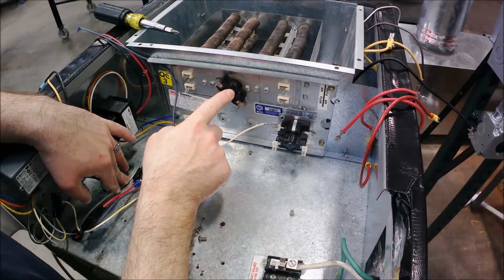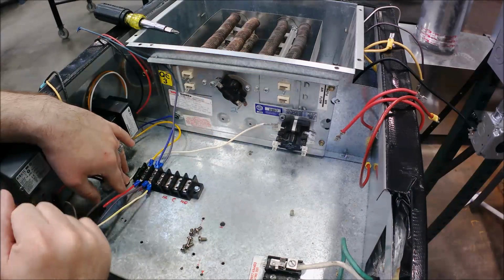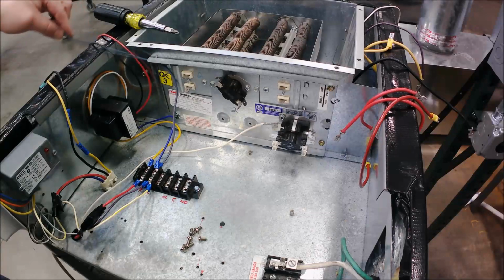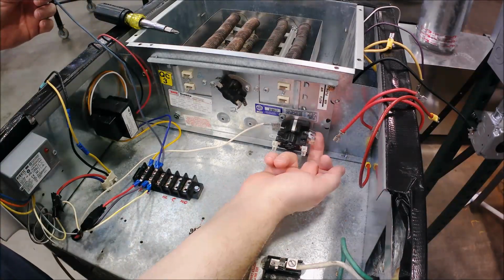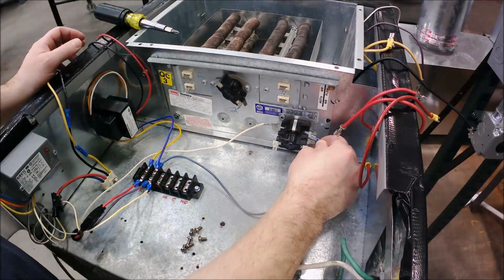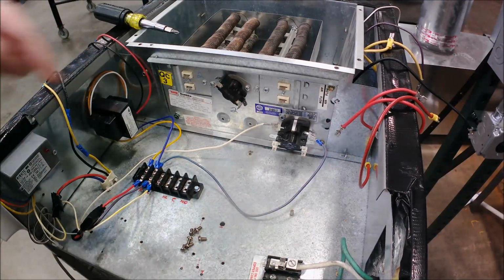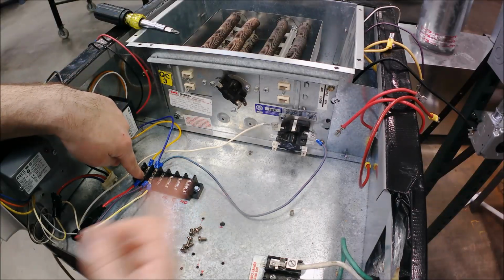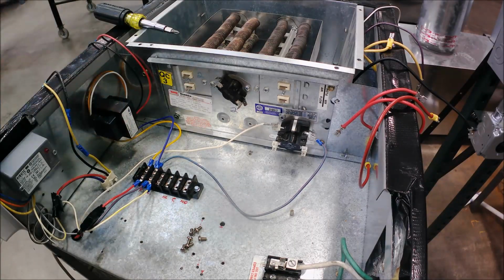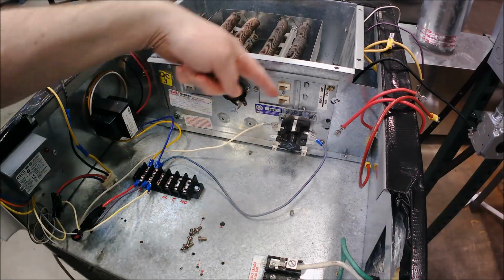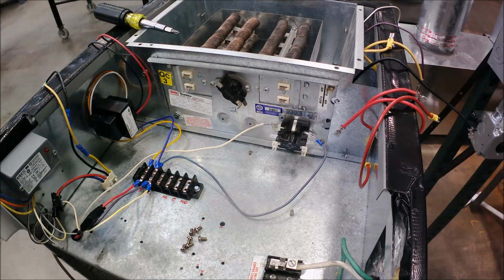These are high voltage limits right here, so we're going to save them for just a minute. So W goes to the heat sequencer, and the other side over here is going to be common back to our transformer. We started on the power source on R. If we're calling for heat and that sequencer is going to be used, then we go R to W inside the thermostat. The W circuit hits here with the hot connection, the 24 volt coil as we'll call it, and then back on common. So that completes that. The relay is done, the transformer connections are done, and the heat sequencer is done.